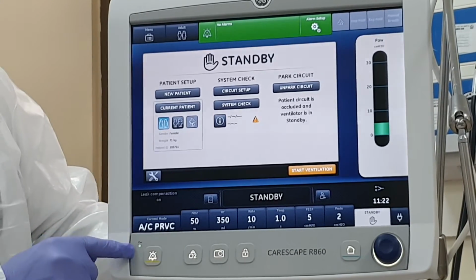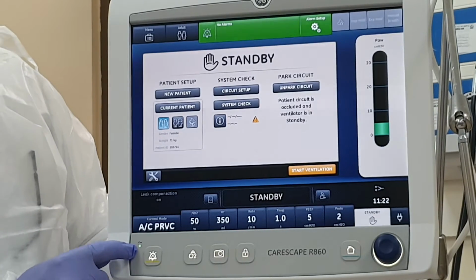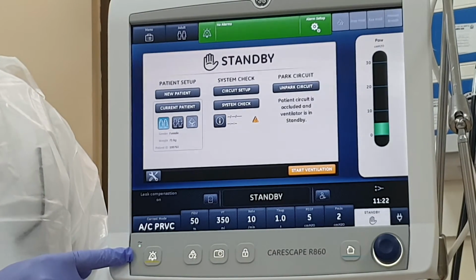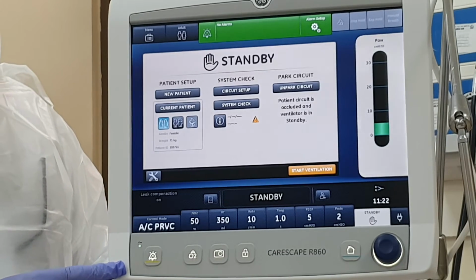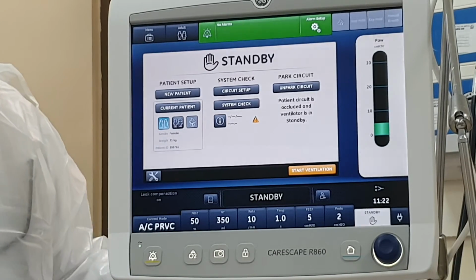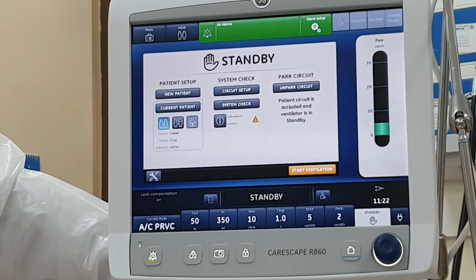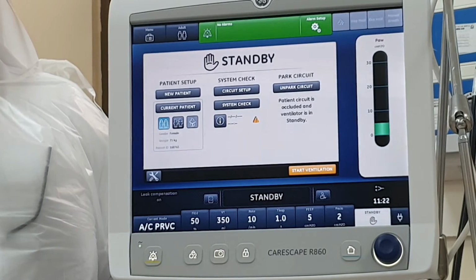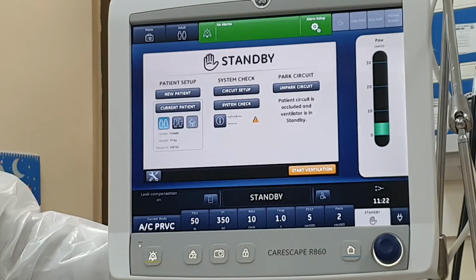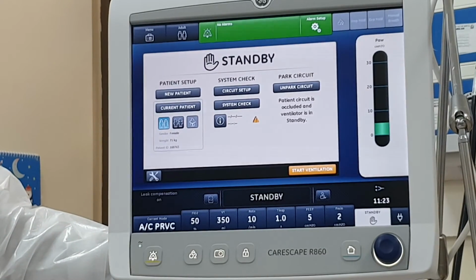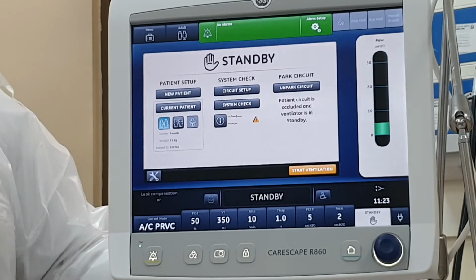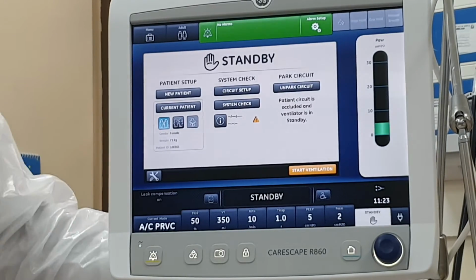And as you can see, there is a current here. It needs to be connected to air and oxygen. Air cannot be generated by the ventilator itself. You could make the ventilator work on one source only, either oxygen or air, but oxygen will give 100 and air will give 21, and it will not change here. It is measuring the input of gas. So even if you increase the oxygen, it cannot increase, and it will keep alarming if the oxygen is not working or something.